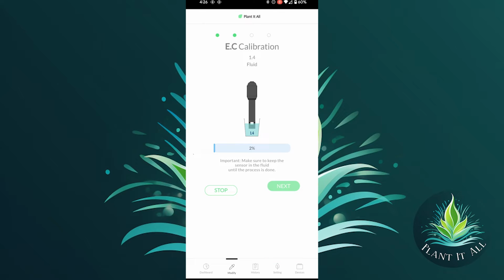Okay, here we go. We are in calibration and we've got a little timer to fill. So the important thing here is to never short this process. If you don't keep the probe submerged in the solution the whole time, you can offset the calibration, and then you've kind of negated the point of doing all of this. So after you have the probe in the solution, you've jiggled around to make sure that there's no air bubbles, just keep it there. Wait out the timer. It's going to fill all the way up, and then we're going to move on to the next step.